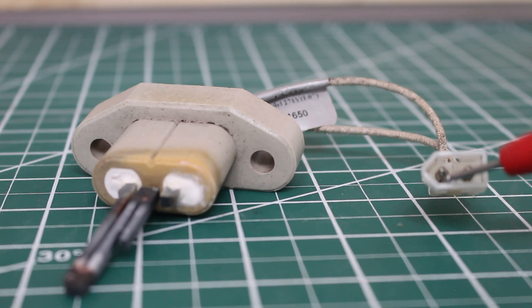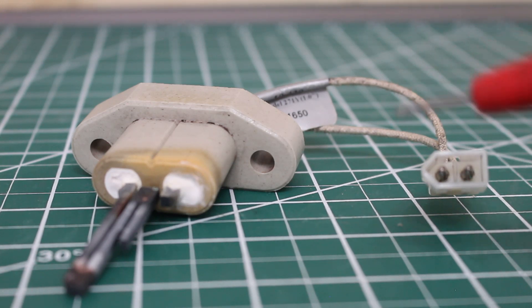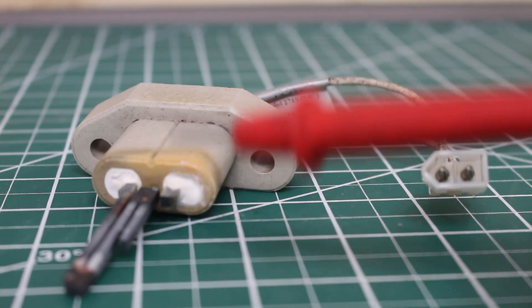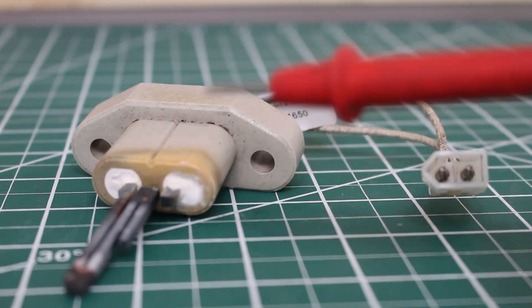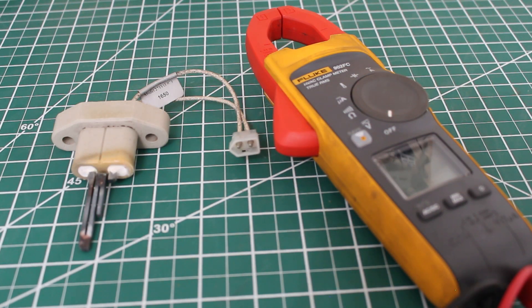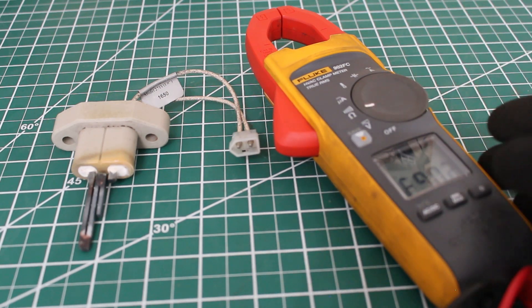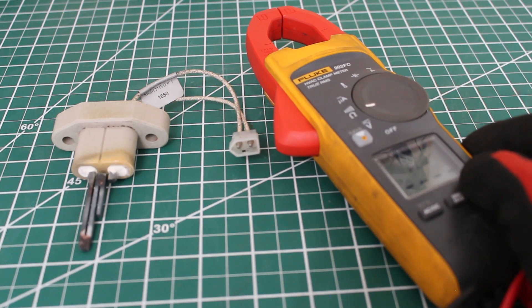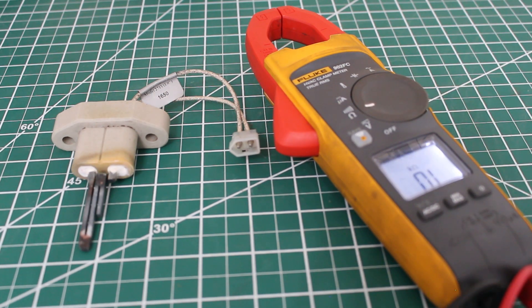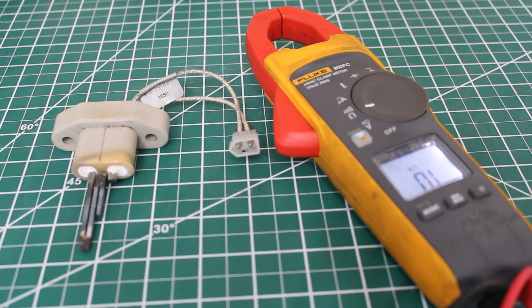With the power off we're going to isolate the hot surface igniter by removing the wires. In this case we have a connector so we're just going to disconnect that so we can get to the two conductors so we can check resistance across the hot surface igniter. I'm using the Fluke 902FC HVAC clamp meter. We're going to set our meter to resistance. For my meter it reads continuity and resistance at the same time.